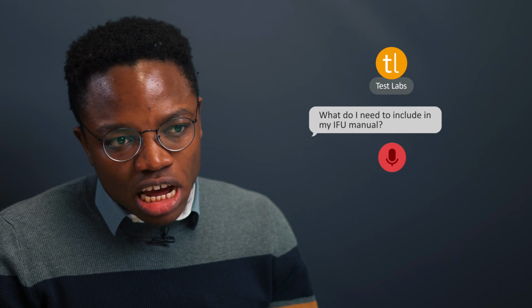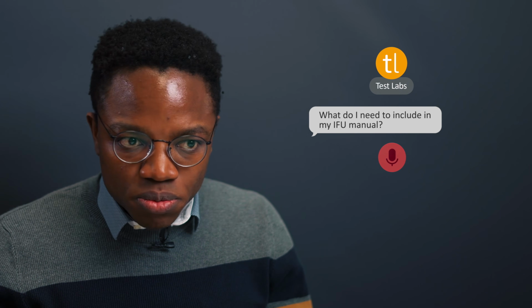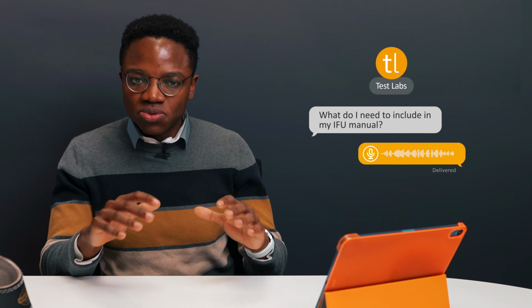I get this one quite a lot actually. What do I need to include in my IFU manual? So this really depends on how much experience you have with the MDR process as a whole. The things that should go in your IFU are very explicit, and they're made clear specifically within the standard code ISO 17664-1 and 2. Those standards will basically detail exactly what needs to go into your IFU, what evidence you need to provide with the contents of your IFU, and how you should go about essentially validating those pieces of evidence. But long story short, you basically need cleaning instructions, disinfection instructions, and sterilization instructions. You also need to state exactly how long of a life cycle you're going to give your device in your IFU, and make sure any maintenance instructions that need to be within that IFU are in there. That's the key point to making sure the end users have a good experience with your medical device.